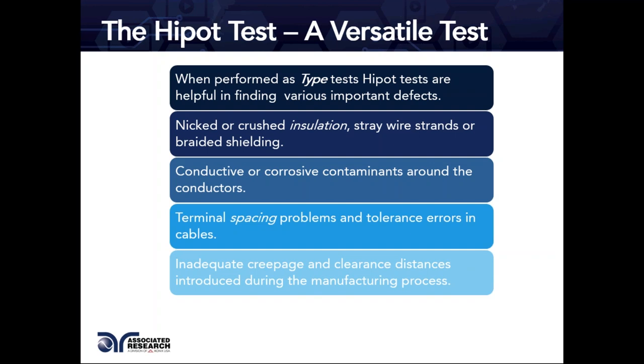Other detectable issues include spacing problems and tolerance errors in cables. If conductors on a PCB are not spaced appropriately, energy can jump between them — something like arcing, which we'll discuss later. Inadequate creepage and clearance distances introduced during manufacturing are also detectable, making the Hipot test a valuable tool for understanding overall product insulation quality.